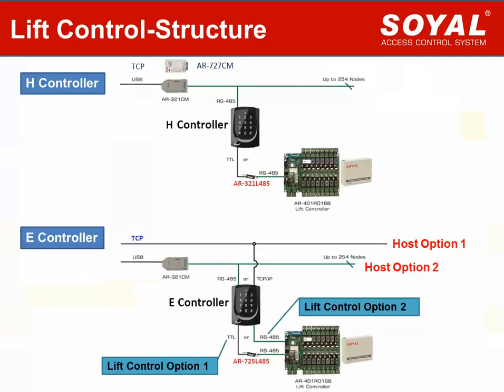This page shows a simple structure for lift control. For H controller, connect it to the lift control board via TTL converter AR-321L485, and connect it to the computer for management via USB converter or TCP/IP converter. For E-controller, there are two options. Option 1: Use TTL converter AR-725L485 between E-controller and lift control board. Option 2: Directly connect E-controller to lift control board via RS-485 host port.